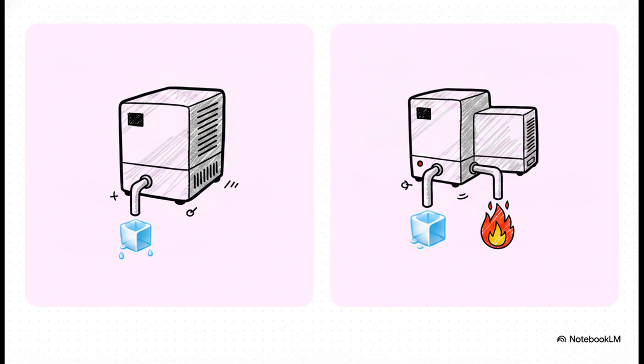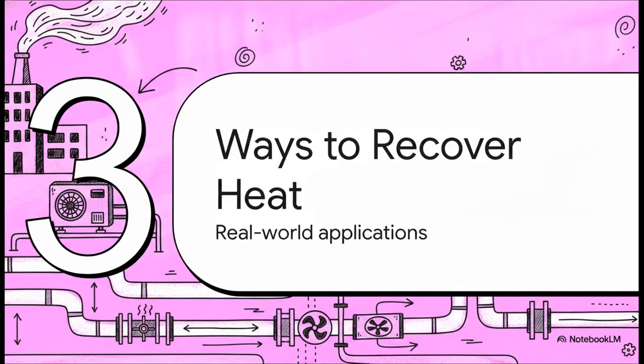A standard chiller is judged solely on how efficiently it produces chilled water. That's it. But a heat recovery chiller has 2 highly useful outputs. It gives you cooling from the evaporator side and heating from the condenser side. You just can't judge these machines the same way because the combined value of a machine doing 2 vital jobs at the exact same time is vastly greater than evaluating it on cooling alone. Section 3. 2 ways to recover heat.